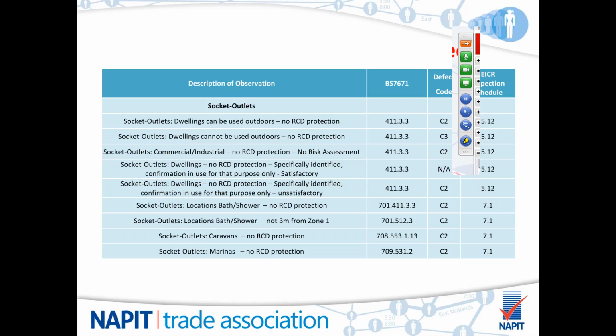Socket outlets within a dwelling that haven't got RCD protection and cannot be used outdoors, then we could just code that down as a C3. Not inherently dangerous. We're not going to use it in a dangerous situation. And as long as we can't see problems with socket drops and cables having very close proximity to holes and kitchen units being drilled, then C3.